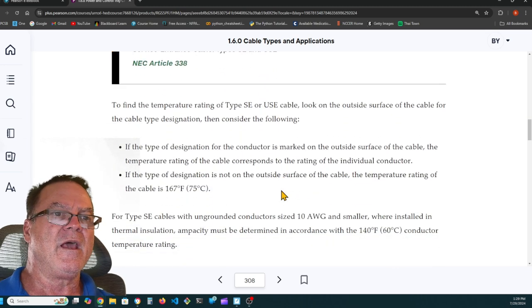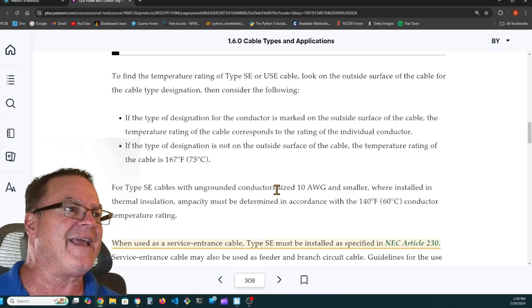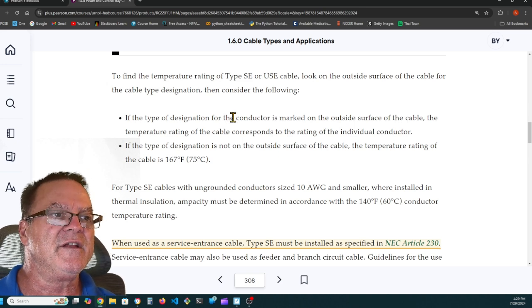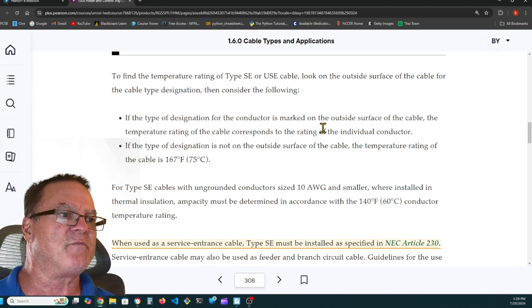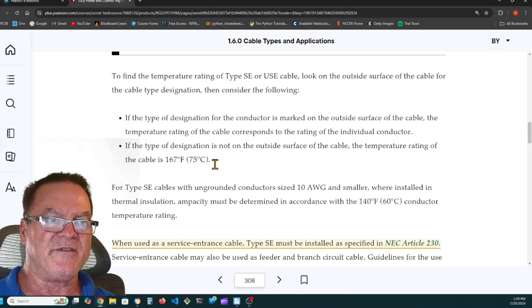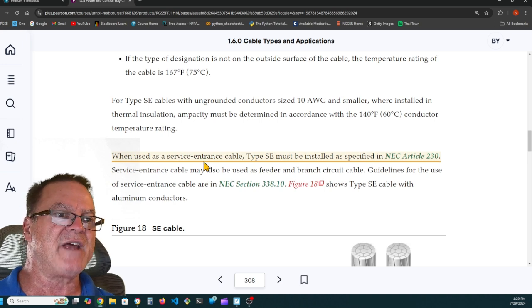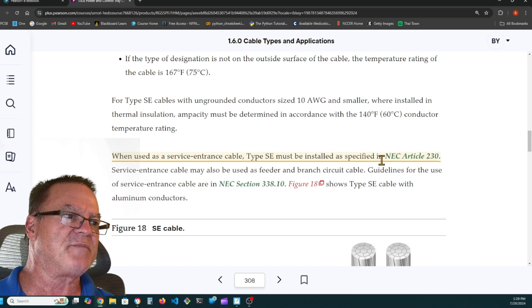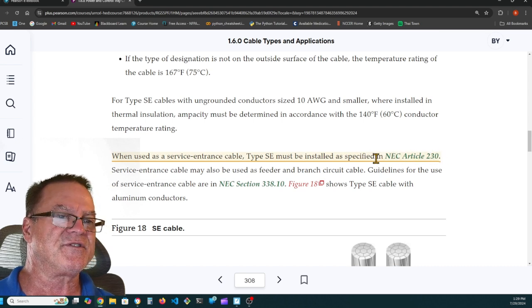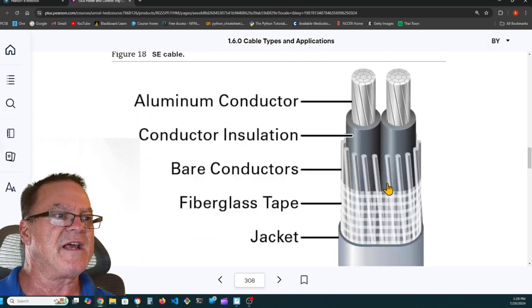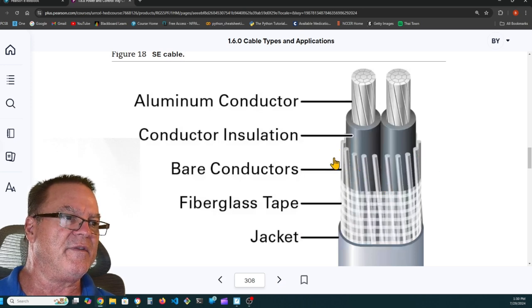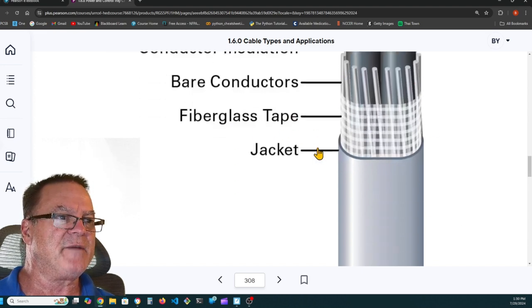underground service entrance. To find the temperature rating of type SE or USE cable, look on the outside surface of the cable for the cable type designation, then consider the following. If the type designation for the conductor is marked on the outside surface of the cable, the temperature rating of the cable corresponds to the rating of the individual conductors. If the type designation is not on the outside surface of the cable, the temperature rating of the cable is 75 degrees Celsius. Here's a highlight. It says, when used as a service entrance cable, type SE cable must be installed as specified in Article 230. Article 230 is about services. So here's an example of type SE cable. The neutral is bare. These bare conductors wrapped around the outside, that's the neutral. So you have 2 hots and a bare neutral. Then there's fiberglass tape, and then there's the jacket.